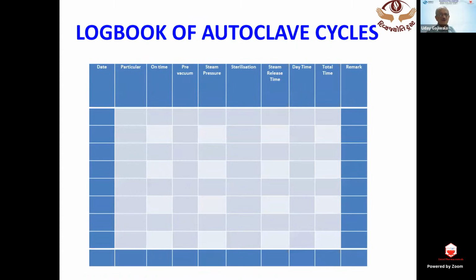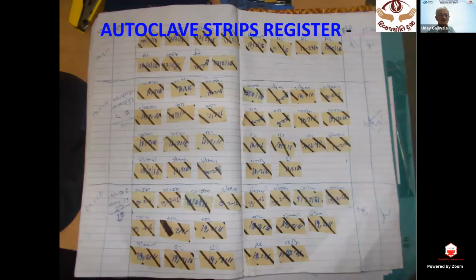This is the logbook of autoclave cycle. This is the one we use for class B, the horizontal autoclave with vacuum cycle. When we turn on the heater, when the pre-vacuum is done, when the steam pressure is attained, how much time was taken for sterilization, when the steam was released, all this is recorded, and it is signed by the person who runs the autoclave cycle and the theater in charge also.